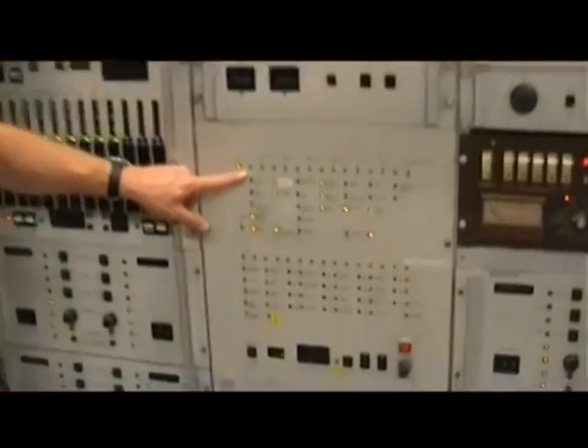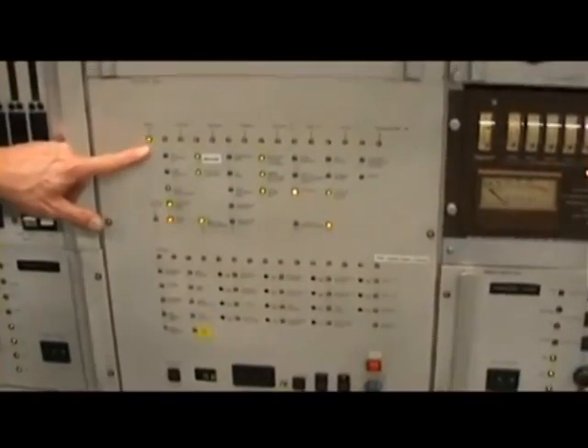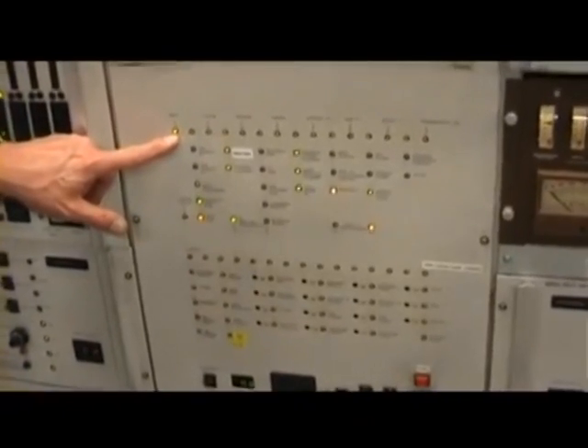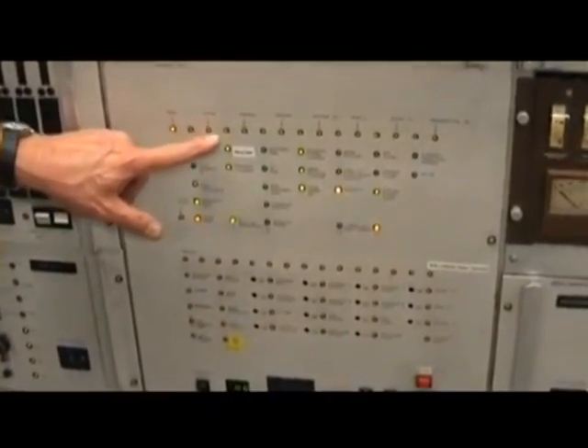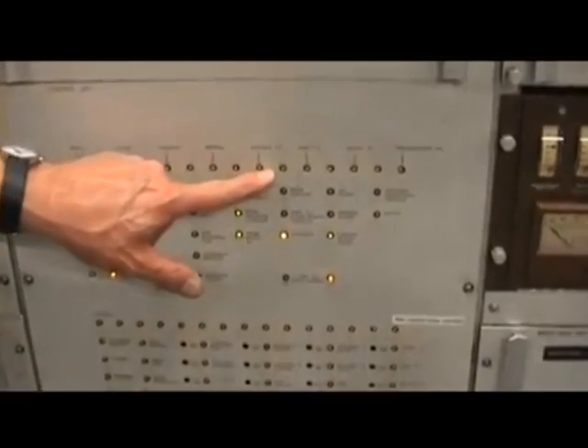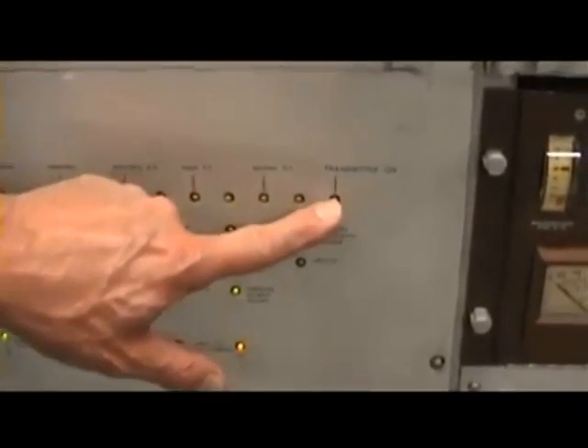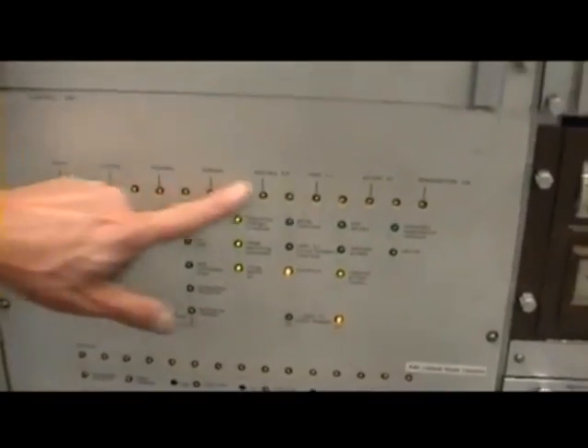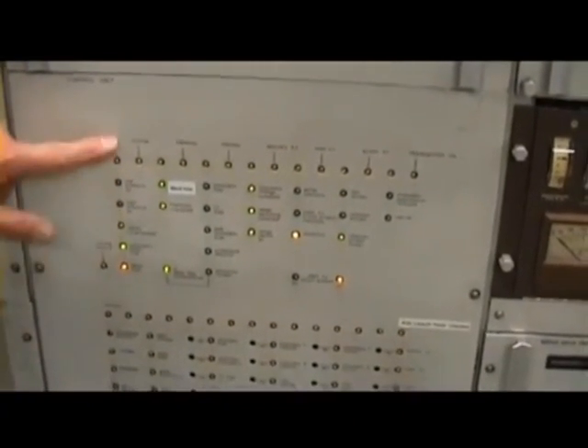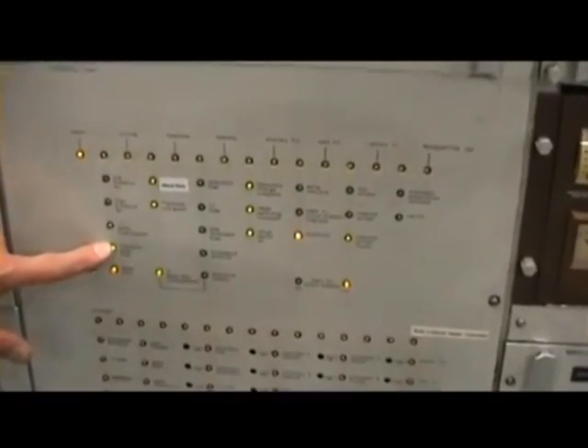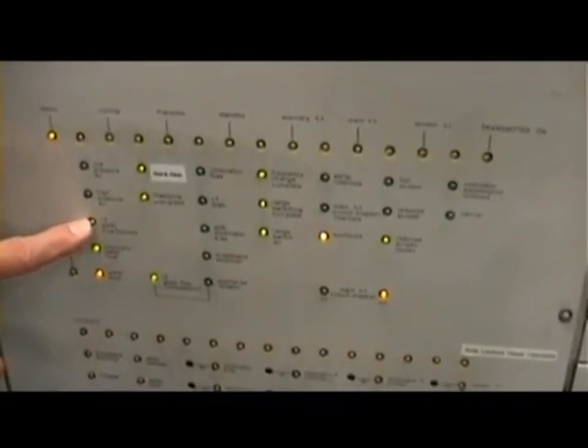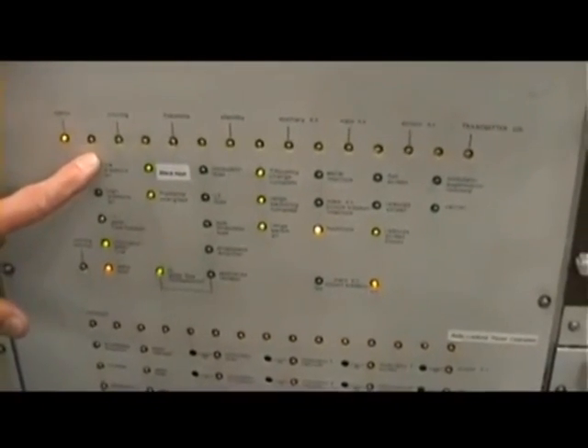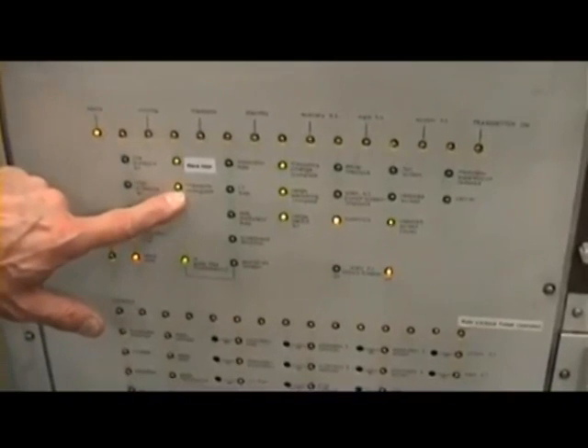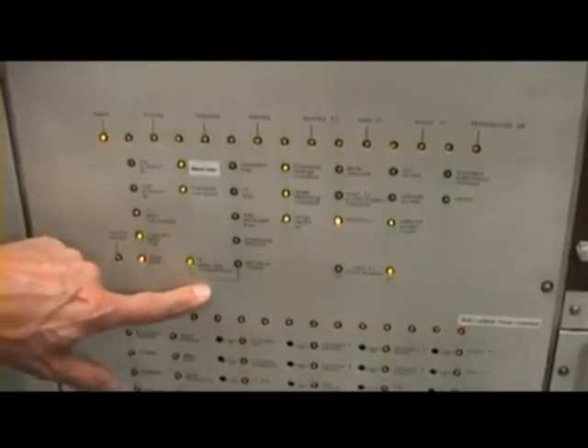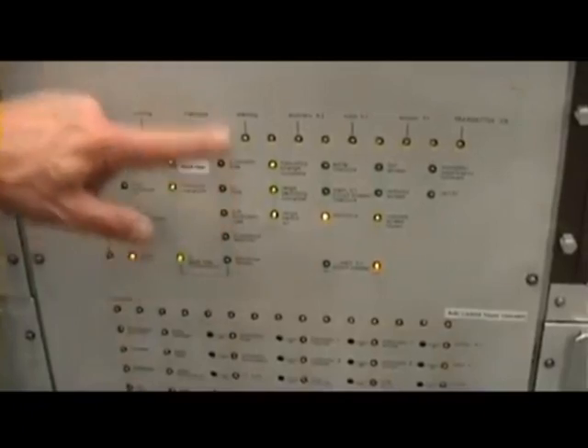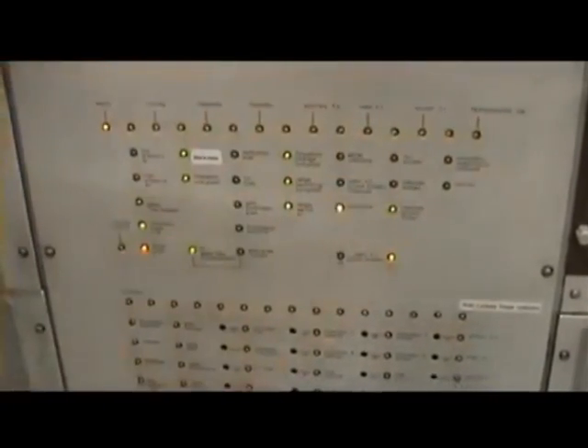Again, the same sort of idea of indication of progress of transmission. Start with, is the mains present? Fairly basic. Then you go through the cooling and the filaments and the standby, aux HT, main HT, screen HT, transmitter on. But to get the yellows at the top here, you need to get the greens below. So have you got water? Have we got modulator water flow? Have we got RF water flow? High pressure air, low pressure air, black heat, filaments are energized, RF flowing through the components. All these supplies need to be on to progress to get the transmitter on the air.